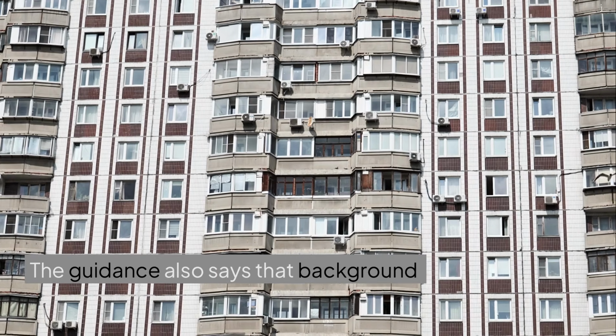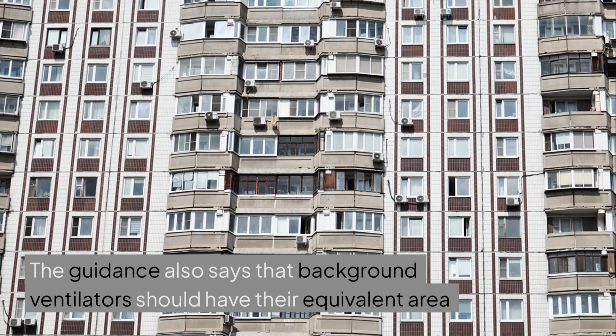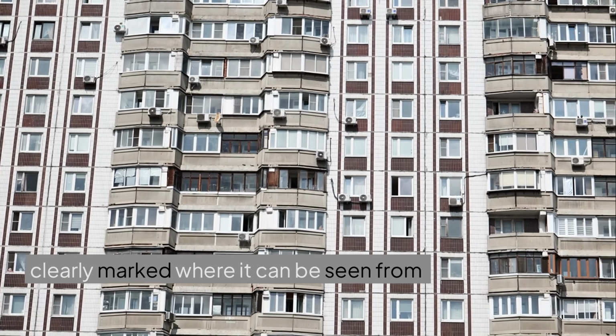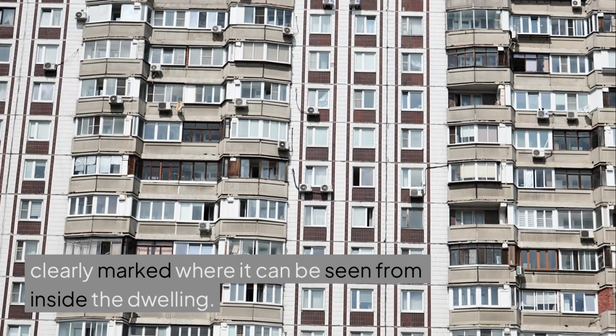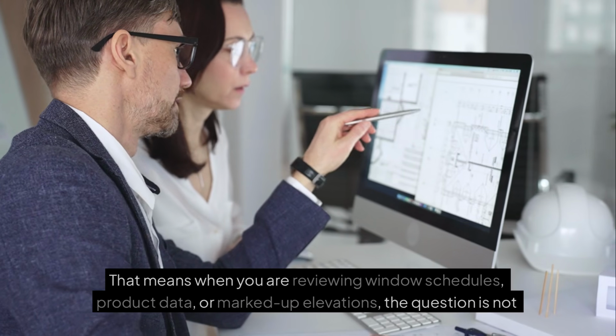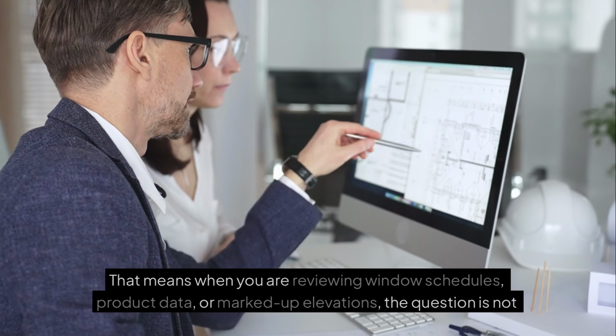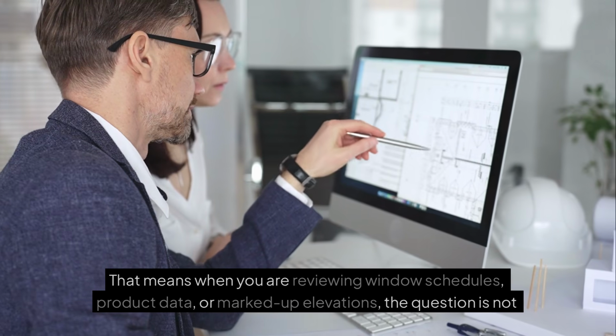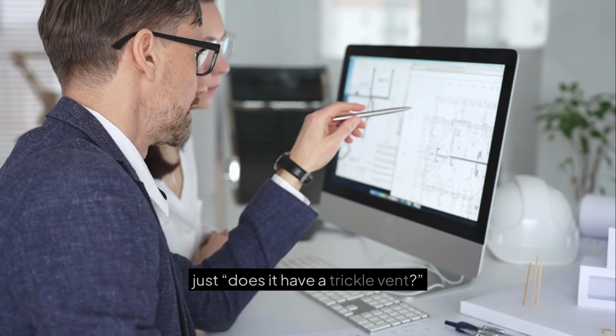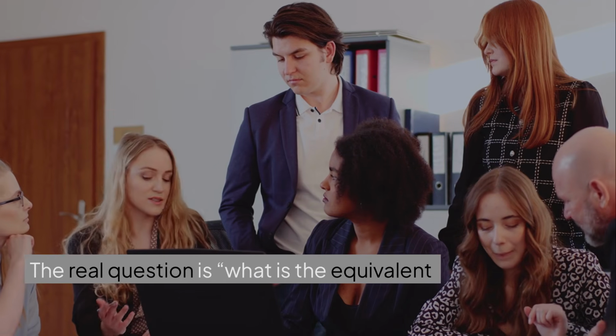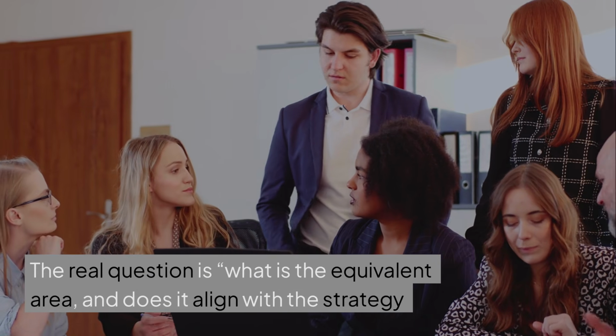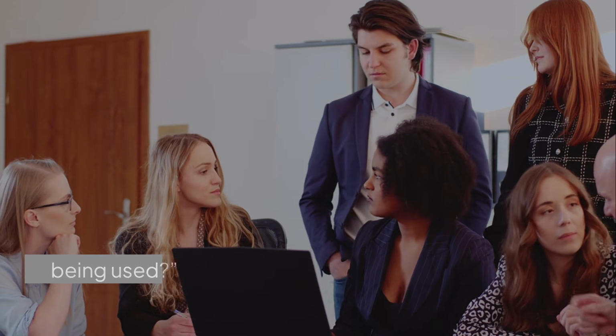The guidance also says that background ventilators should have their equivalent area clearly marked where it can be seen from inside the dwelling. That means when you are reviewing window schedules, product data, or marked up elevations, the question is not just, does it have a trickle vent? The real question is, what is the equivalent area, and does it align with the strategy being used?